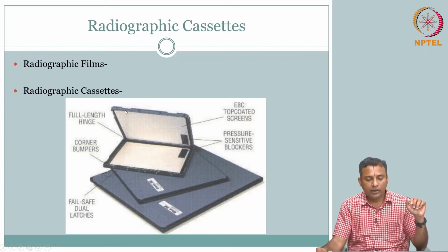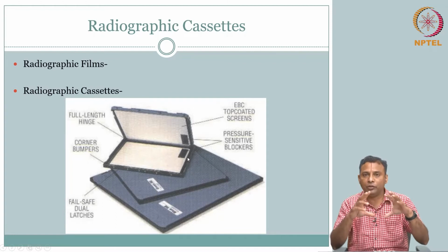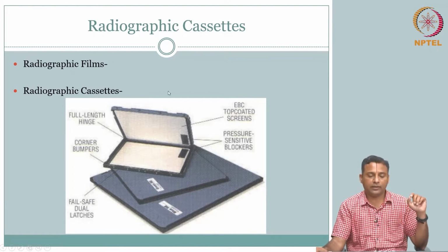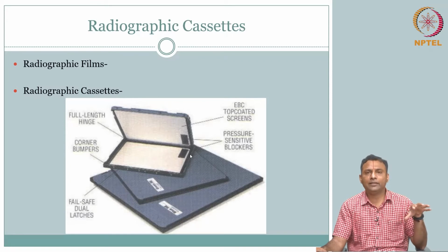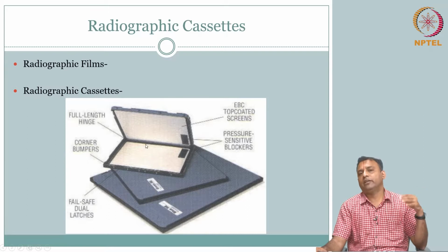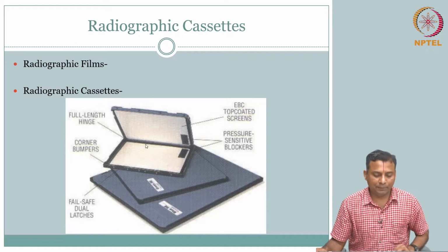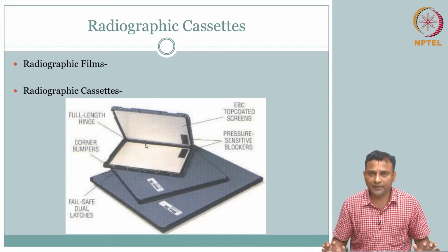Okay. Of course, it has all these mechanical design aspects, so that when you handle it you do not squish it and things like that. But otherwise, this is something that is very common. In fact, it is very common in most centers for quick X-ray diagnosis, but nowadays there is a rapid transition to digital X-ray, which we will cover separately. Clear? So, so much for the instrumentation of it.